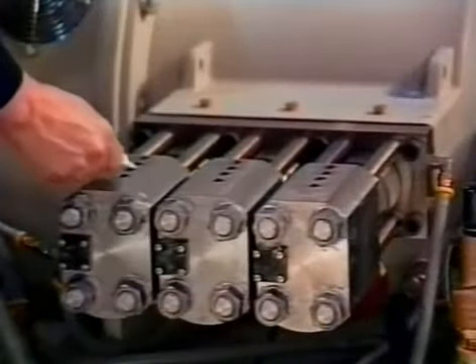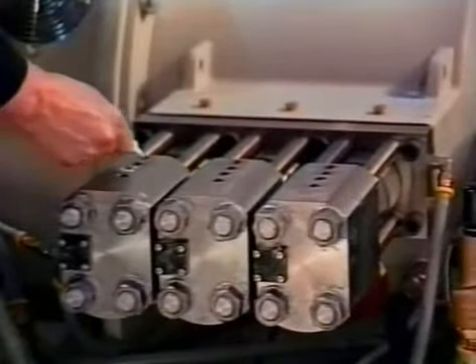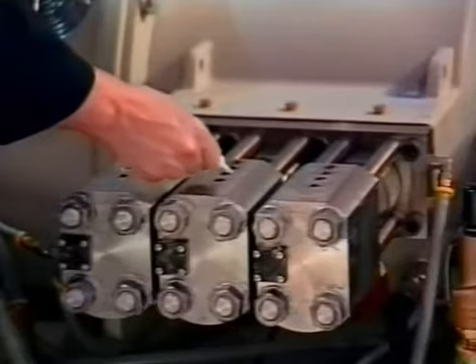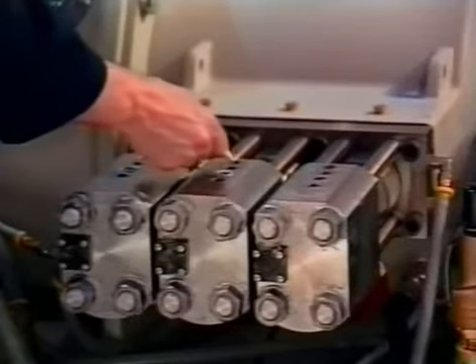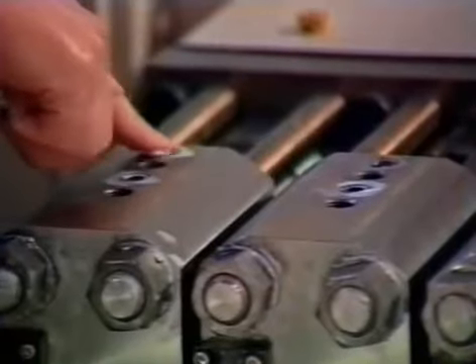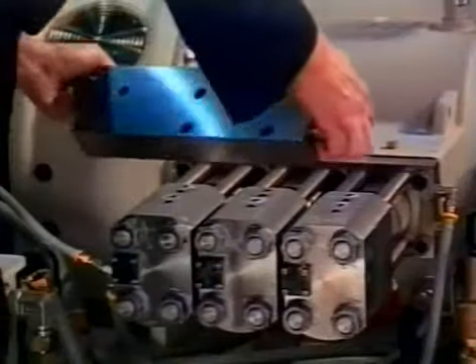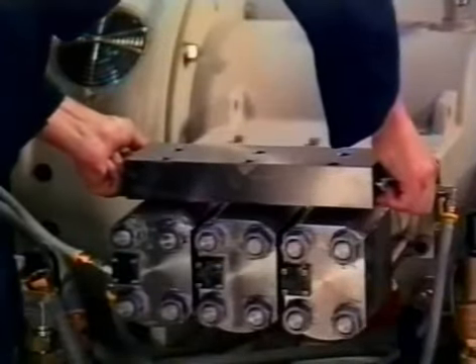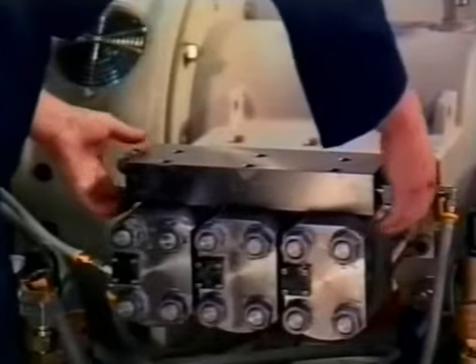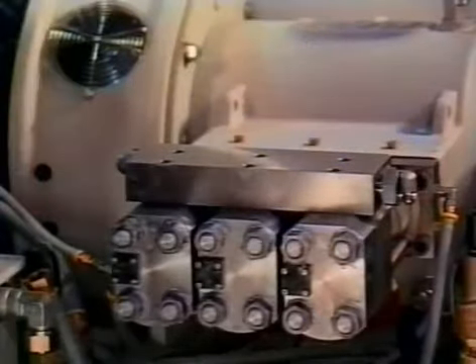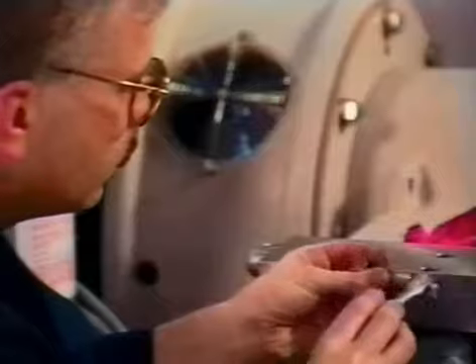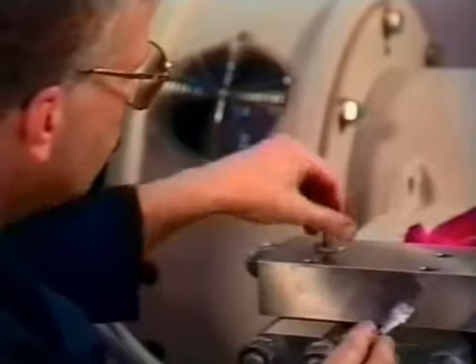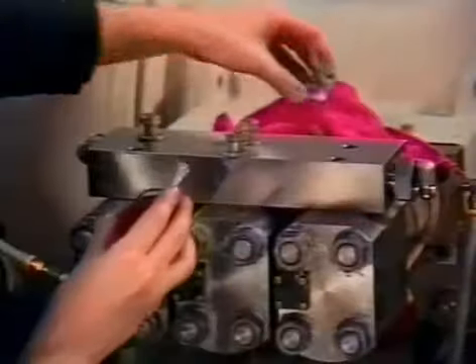Apply white food-grade lube over the O-rings and backup rings. Place the manifold onto the end caps. To prevent damaging the O-rings and backup rings, avoid sliding the manifold on the end cap surfaces. Apply silver anti-seize to the threads of the 6 manifold bolts. Also apply silver anti-seize to both sides of the washers. Torque the bolts to 10 foot-pounds.